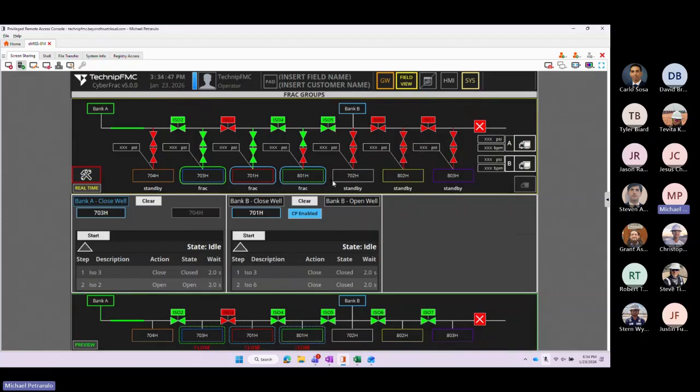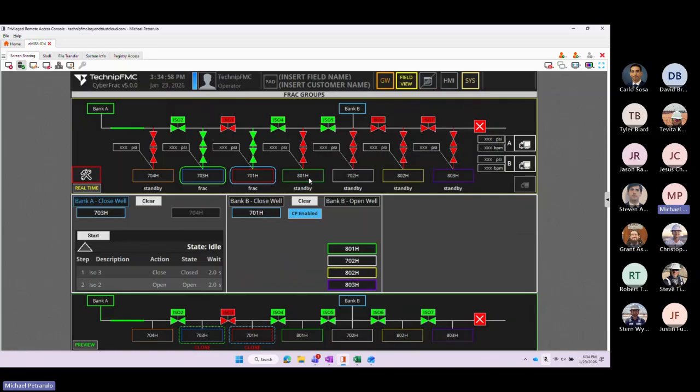We're now part of the way through closing 801. This is actually a good explanation point. I'm going to finish my train of thought before I dive into what just happened. The ISO sequencer was not designed to close valves after they've been opened. It is designed to close valves based on setting its own territory so that pressure can be maintained in the right locations. It will not close on flow path, and it will not open itself into another bank's flow rate.